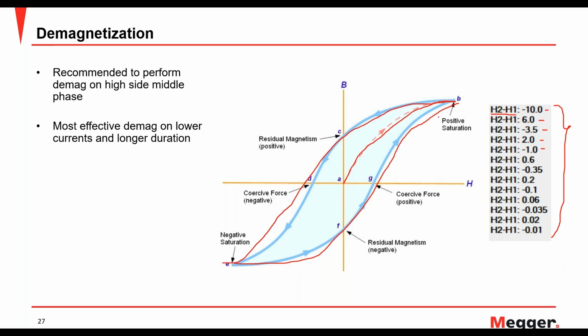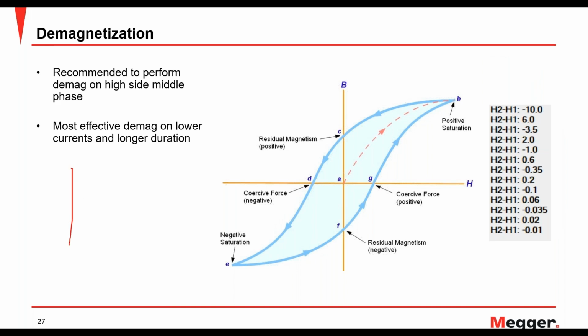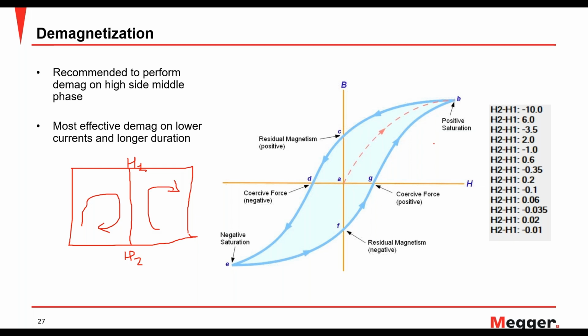The reason behind that is usually your transformer is a three-legged component, so it's something like that. And you have your middle leg right here, and this is your H2 H1. In that case, your H2 and H1 winding would be on your middle leg, and this is where you demag from. So it is easier to remove the flux in both directions from the middle leg rather than working on each side. So that's why you always do it on the middle leg to easily remove the flux from both directions.